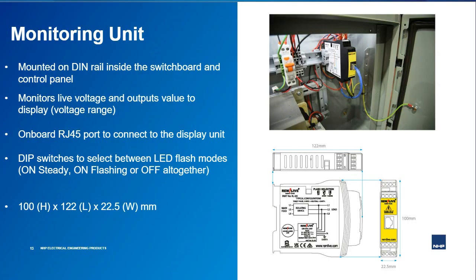Let's look at the components in more depth, including some of the features that they have. As mentioned before, the monitoring base unit is mounted to DIN rail and located inside the switchboard or control panel. It monitors the voltage of the circuit it's wired to, with the new REMLIVE model able to monitor voltages from 24 to 1000 volts. More on the ratings a bit later in the presentation. For the circuit being monitored, if voltage is detected between any two conductors in the specified range, then this unit outputs this to the display and the LEDs on the display light up.